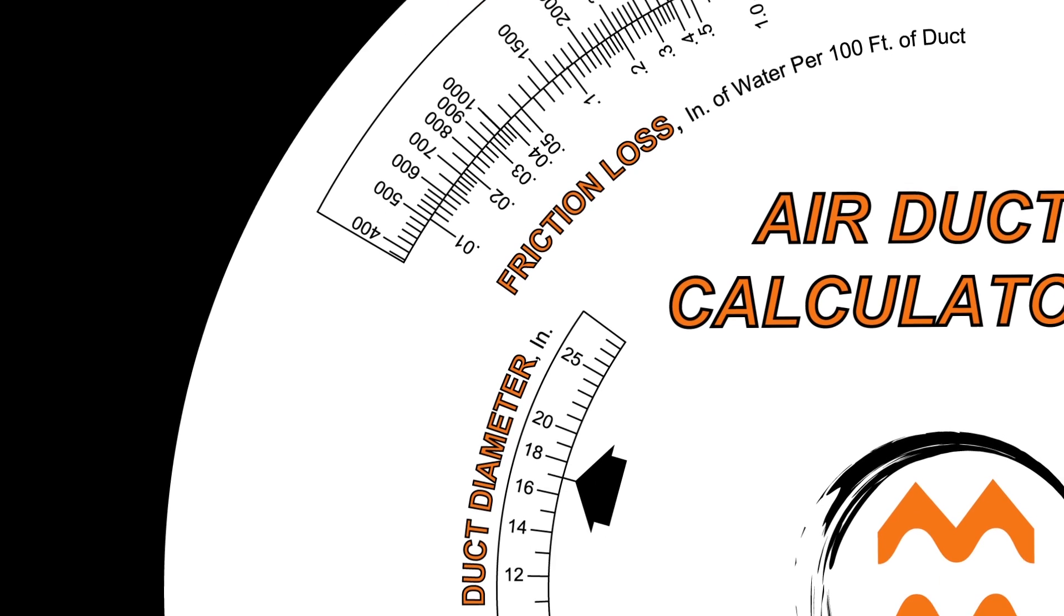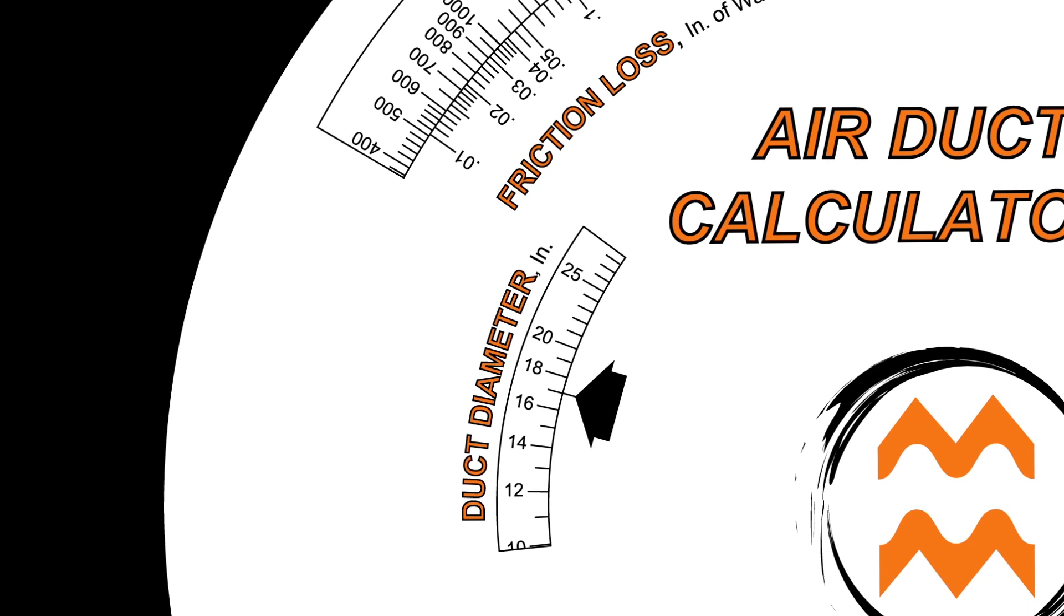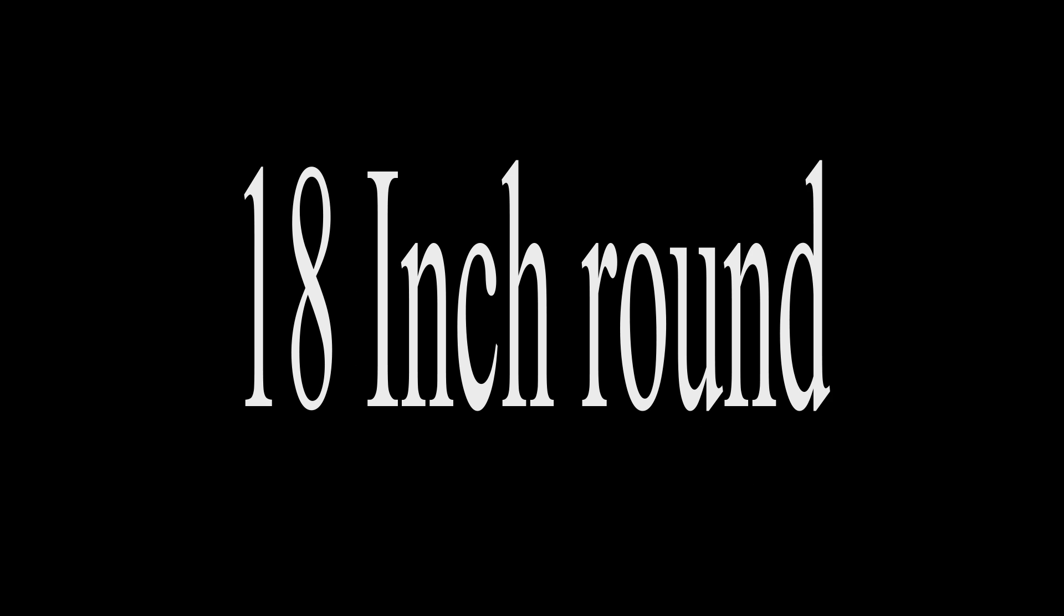Looking over to the duct diameter window, you're instructed to use a 17 inch round duct. Now, most available duct sizes will force you to round up to a more industry standard size. In this case, an 18 inch round duct is best for your design.